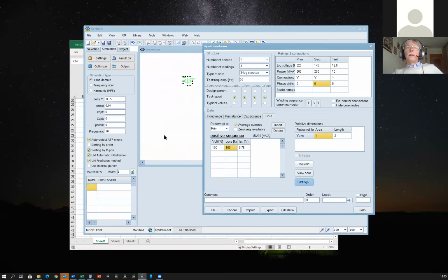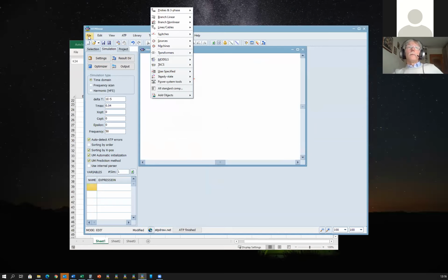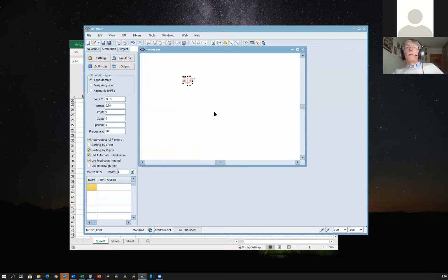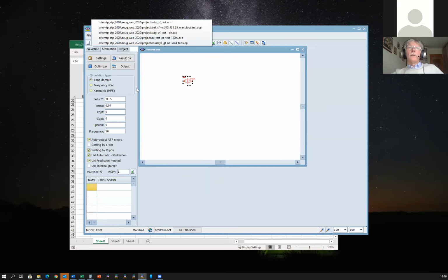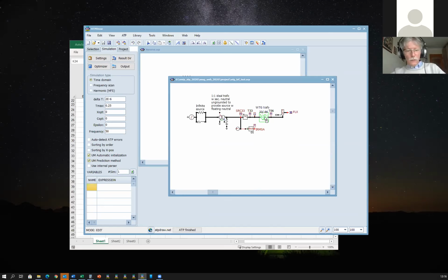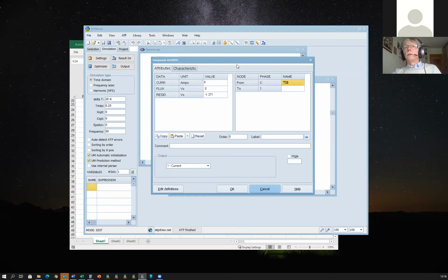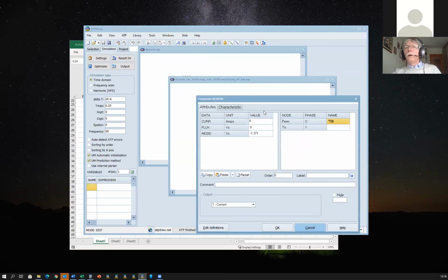Whereas in the case of BC-TRAN modeling, you have full access to the externally connected type 93 nonlinear inductance, and you can set the residual flux as I showed to you. I think it is set here. Yeah. No such option exists with the hybrid model, or at least I don't know how to set it.